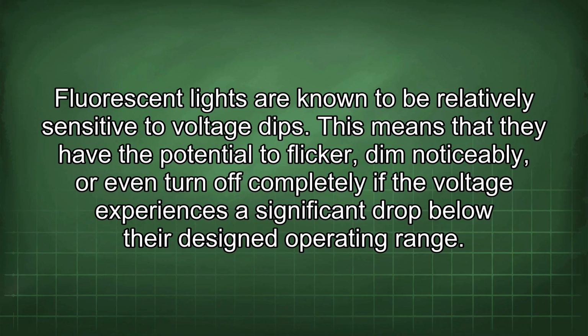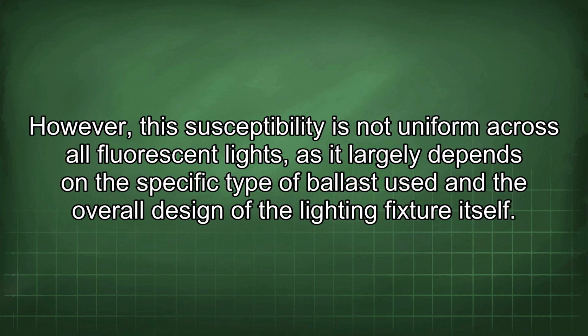Fluorescent lights are known to be relatively sensitive to voltage dips. This means that they have the potential to flicker, dim noticeably, or even turn off completely if the voltage experiences a significant drop below their designed operating range. However, this susceptibility is not uniform across all fluorescent lights, as it largely depends on the specific type of ballast used and the overall design of the lighting fixture itself.